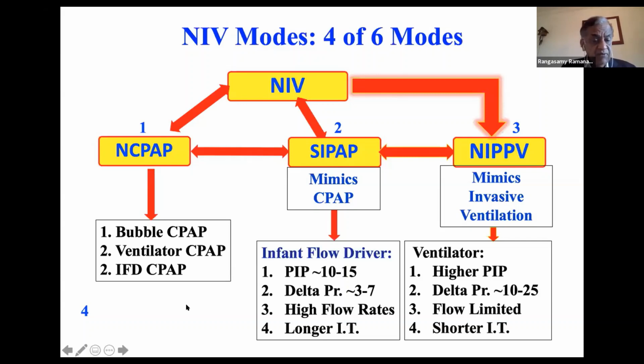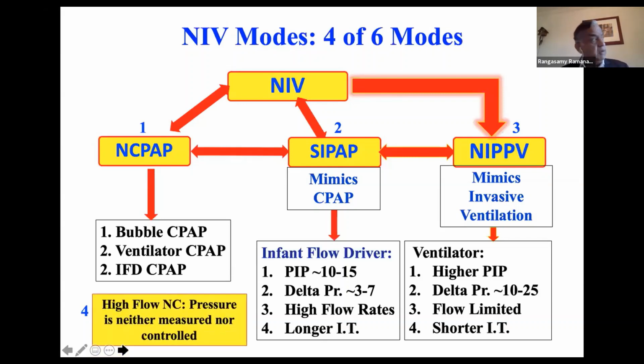Next mode is the high-flow nasal cannula. The problem with high-flow nasal cannula is that it's very easy to use, but it causes lots of injury to babies because the pressure is neither measured nor controlled by you. So depending on the size of the nostril, depending on the size of the cannula, you will deliver different pressure. Okay, so flow rate and the size of the baby, all of them will impact how much pressure gets delivered to the baby. And there's no way for you to measure the pressure when you're on high-flow nasal cannula.